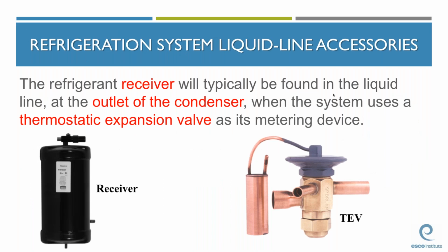On the refrigeration cycle and accessory front, make certain that your students are well aware of system component locations in the system, especially the refrigerant receiver, as this is an important component with regards to refrigerant handling. Of course, you'll only find refrigerant receivers on systems that are equipped with modulating metering devices, such as thermostatic expansion valves. Since the receiver is located at the outlet of the condenser, the state of the refrigerant at the inlet and outlet of the receiver is, on a properly operating system, a high pressure, high temperature, subcooled liquid.